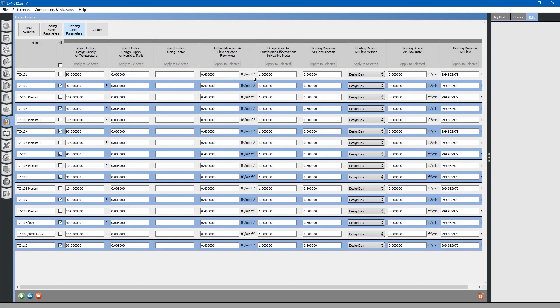Likewise, using the ASHRAE ventilation rate procedure, if we have overhead air distribution, we would probably want to change this to 0.8 for distribution effectiveness. Apply these to the other areas as well.